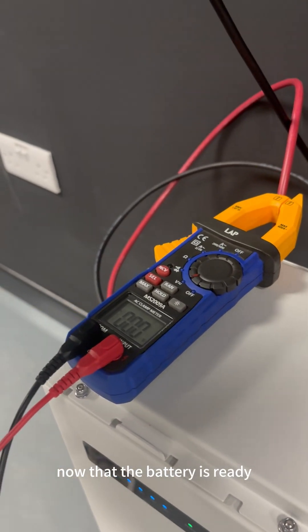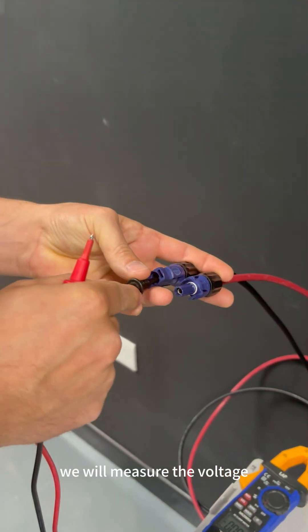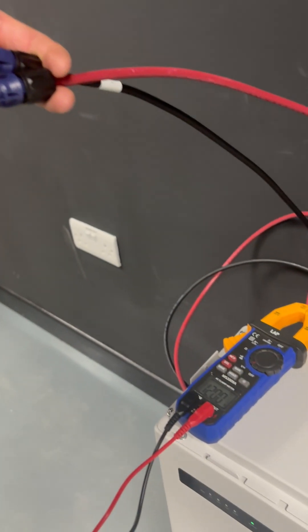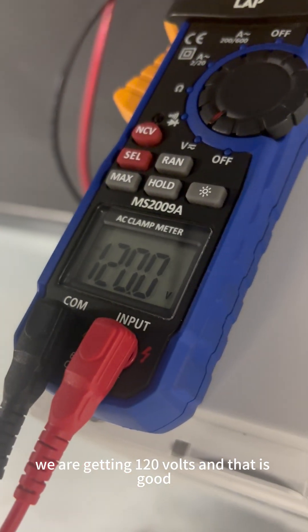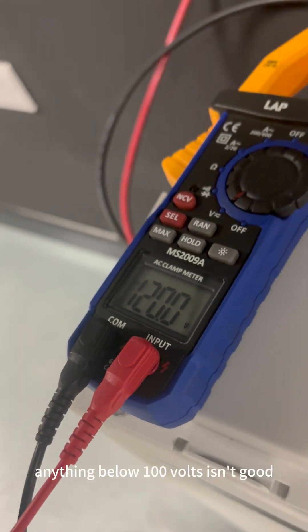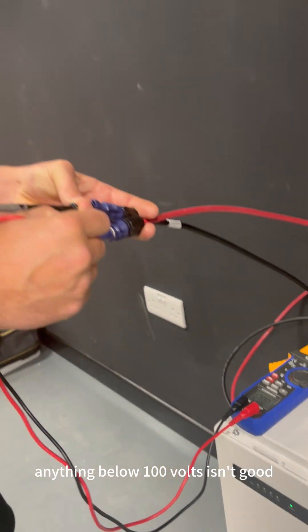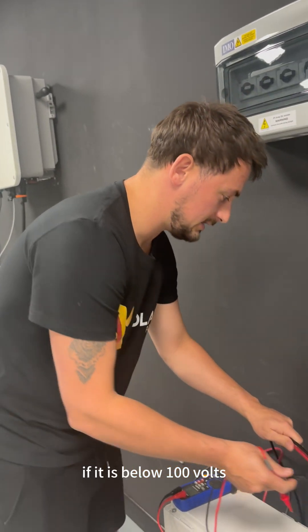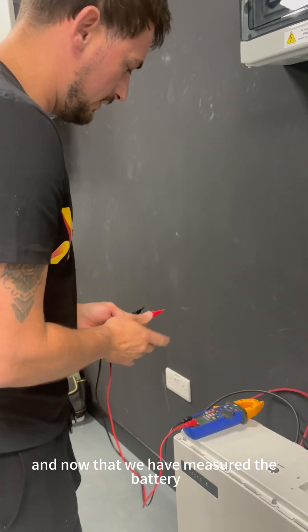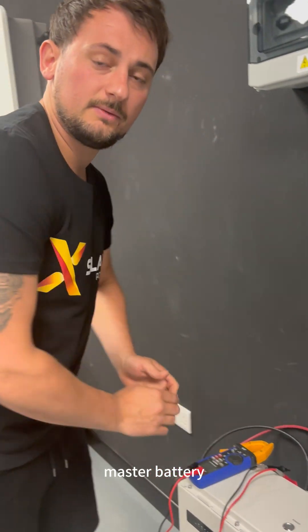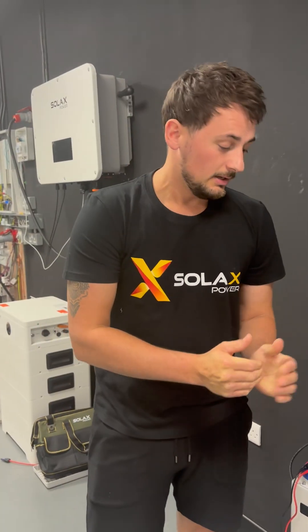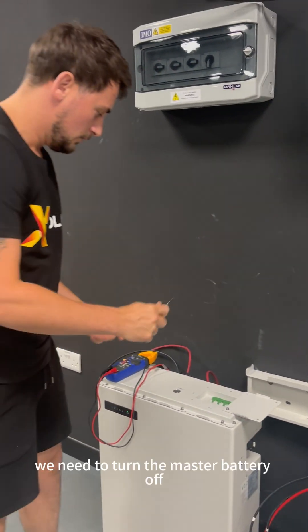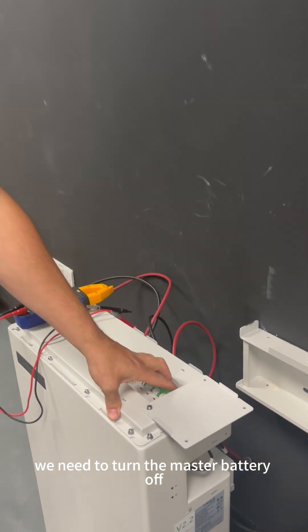Now that the battery is ready we will measure the voltage on the DC cables from the battery and you can see we are getting 120 volts and that is good. Anything below 100 volts isn't good. Please take a picture of that if it is below 100 volts. Now that we have measured the master battery, that is okay. Now it's time to measure the slave battery, but first we need to turn the master battery off.